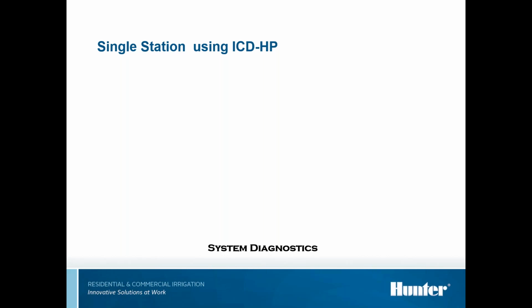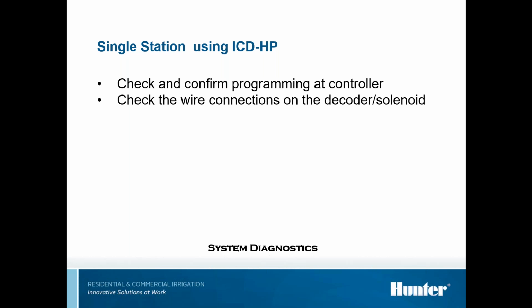Using your ICDHP, if you have one, you can check and confirm the programming that is on the decoder that the controller is supposed to be seeing. Make sure your station number is correct and everything is like it's supposed to be. Check the wire connections from the decoder to the solenoid again. Check the decoder to solenoid with the ICDHP.